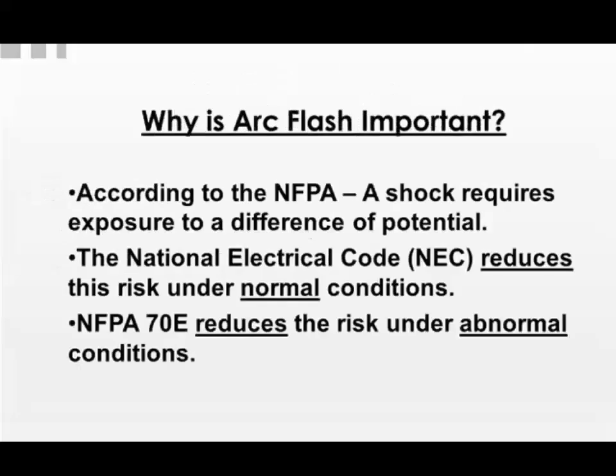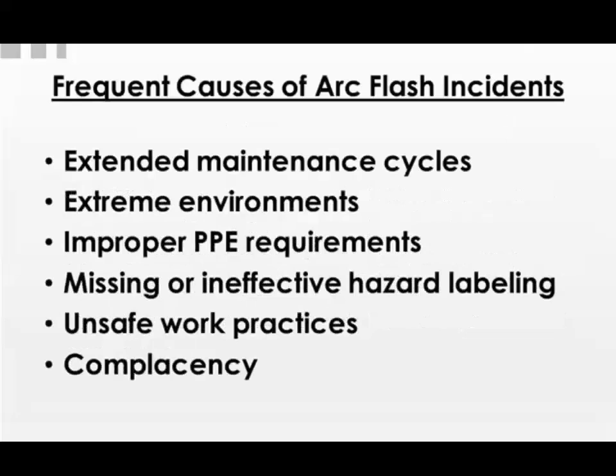So why is arc flash important? Well, according to the NFPA, a shock requires exposure to a difference of potential. The National Electrical Code, or NEC, reduces this risk under normal conditions, but NFPA 70E reduces this risk under abnormal conditions, in which an arc flash or an arc blast can occur or will occur. Some frequent causes of arc flash incidents, and this is by no means an all-inclusive list, but covers some of the highlights. Extended maintenance cycles, so putting off preventive maintenance when it should be done.